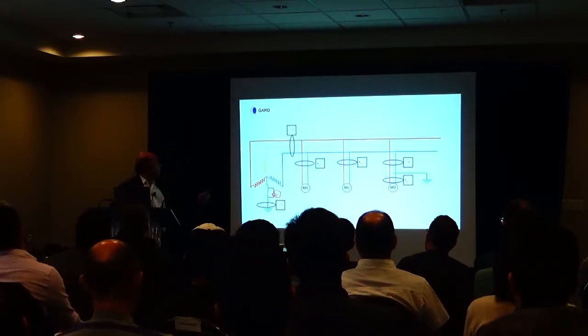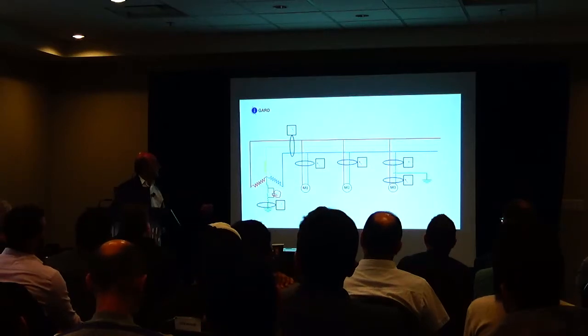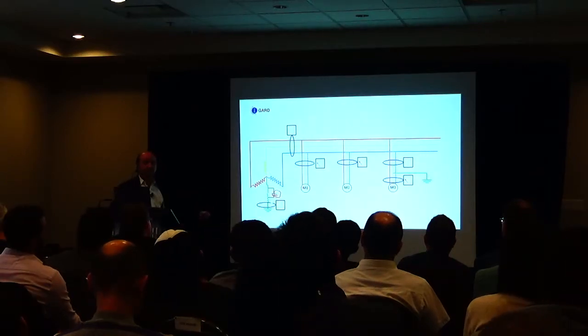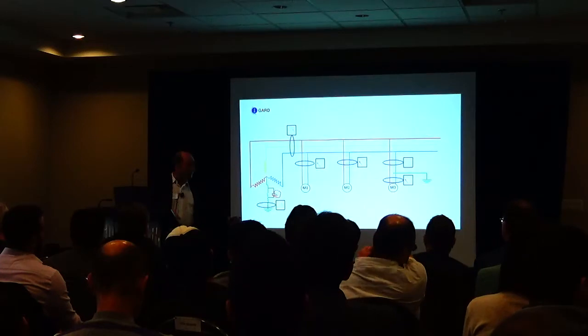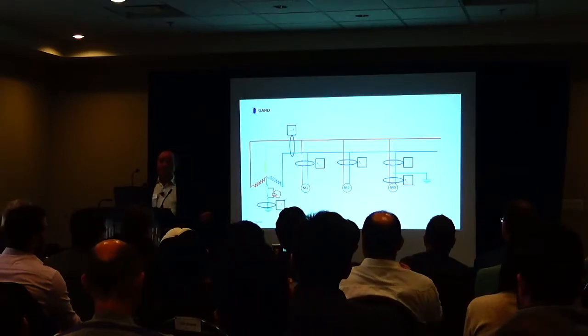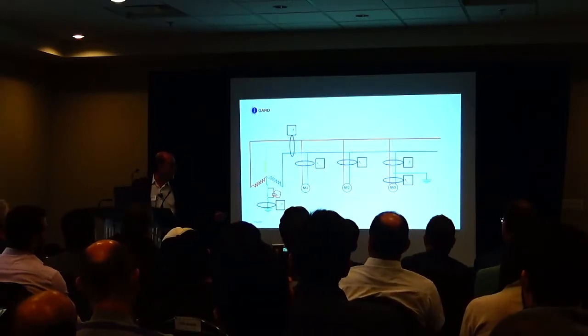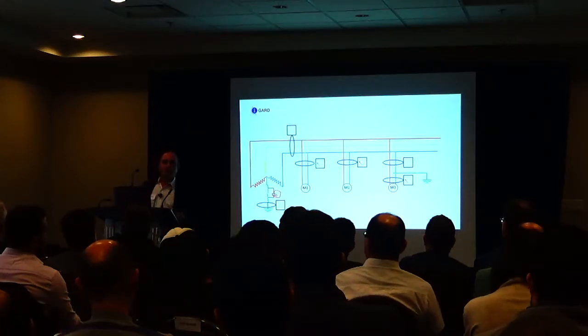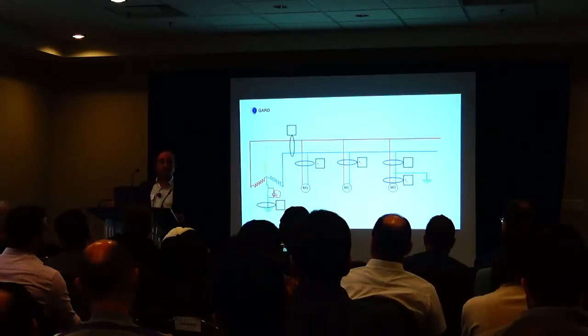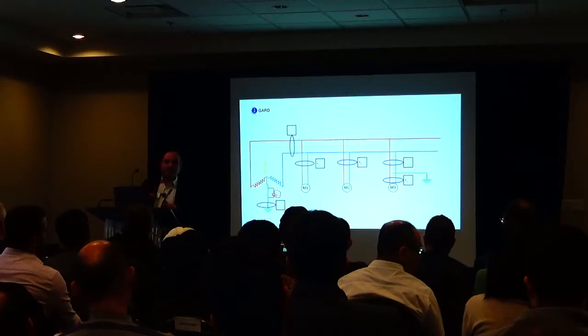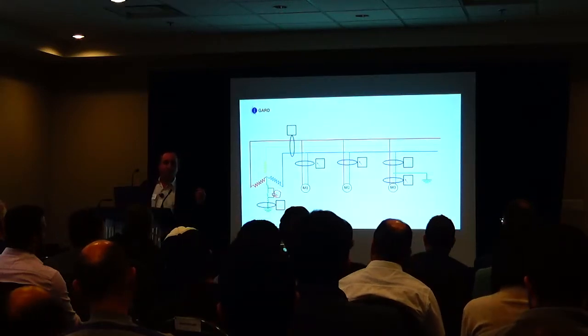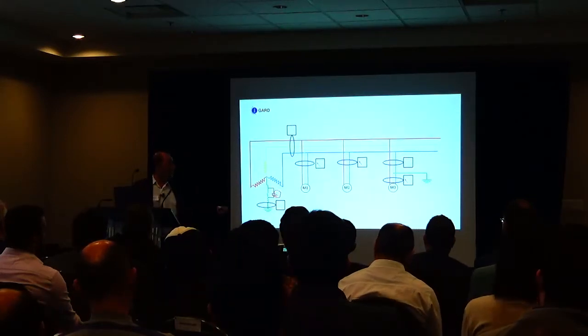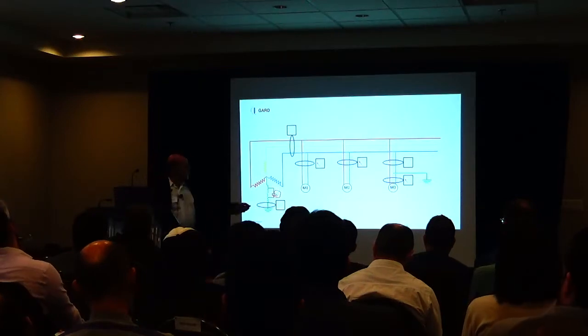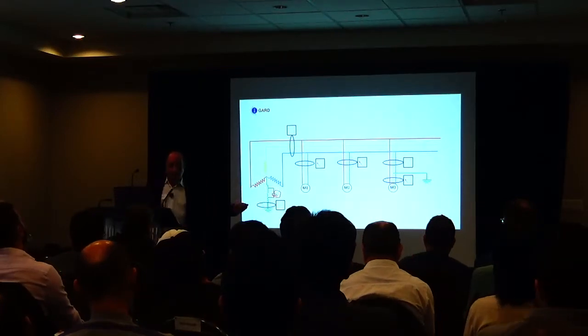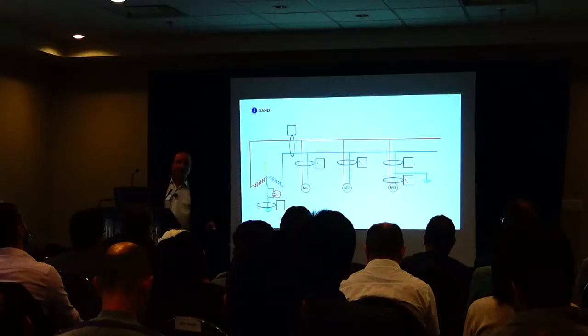So we're still pulsing. We found where the fault is. We can clear the fault if we want to and switch back to a resistance grounded system. We can repair that fault because typically, if you have a fault, it's going to be in a motor. It's going to be in the terminal box. You can open it up, tape it up, put it back into service. No damage at the point of the fault. Had this been a solidly grounded system, there'd be smoke coming out of here. You would be able to find the fault, but that motor's gone.